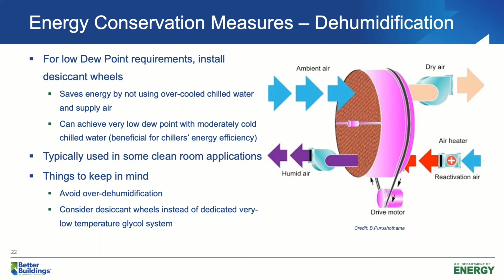Desiccant wheels can help you to achieve very low dew point with a modest chilled water temperature, but they do have some energy penalty because desiccant wheels need some heat for the reactivation process. Do you see the air heater on the right? When talking about dehumidification, we always would like to make sure that we are not over dehumidifying the air, because even though desiccant wheels are pretty efficient in terms of dehumidification and have very low maintenance, they do have some energy penalties.